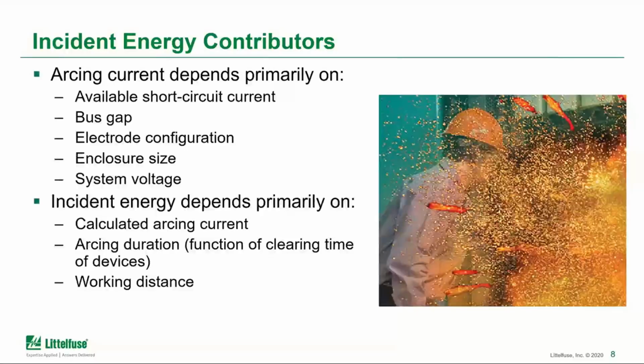When we look at the incident energy, we look at the arcing current that we just talked about, and now we add the time and the distance from the arc. So in the testing, the arcing duration, so that time, has approximately a linear relationship to the incident energy. So if we can react quicker, we can reduce the total amount of energy that's released from a fault. So when you look at these factors, how much control or influence do we have over the voltage or the current or the arc gap if we're doing a retrofit? Those are things where there's not a lot of leeway, and especially in the retrofit stage, time is one of the critical items to address.